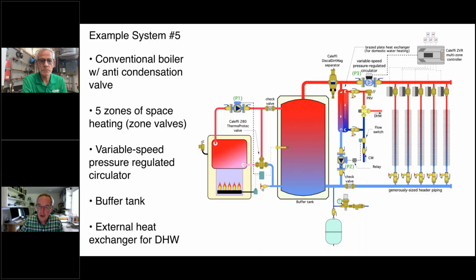Basically, this is going to drive flow through the primary side of that stainless steel heat exchanger and put it right back in a tank. And the cold domestic water gets a single pass through that heat exchanger, and it can be fully warm. So if the heat exchanger is sized correctly, it's basically an on-demand or an instantaneous way to heat the domestic hot water. This detail is used widely in Europe.